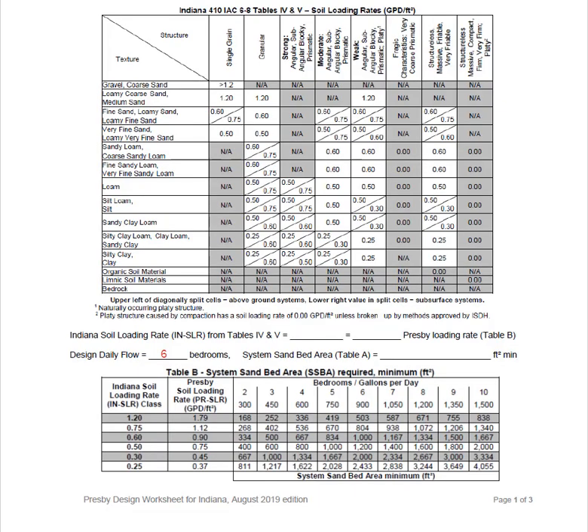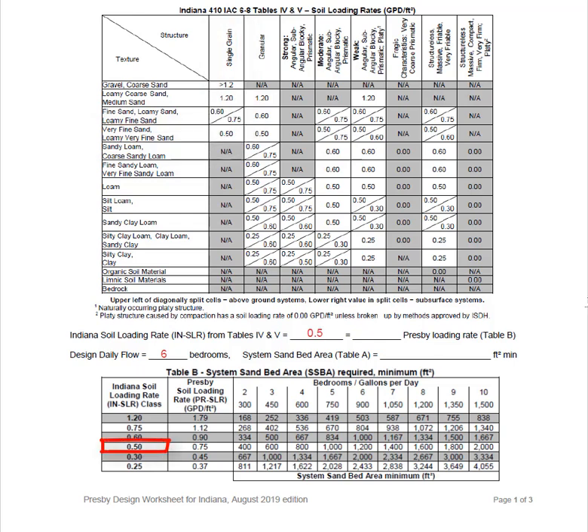In step number two, we're going to calculate the minimum system sand bed area. Let's find the row with very fine sand and then find where it intersects with the single grain column. This value is 0.5 gallons per day per square foot. Now let's find the corresponding Presby loading rate in table B. Once we find 0.5, we move directly to the right and find the Presby loading rate, which in this case is 0.75 gallons per day per square foot. We will start at the 0.75 loading rate and move to the right until we intersect the column for six bedrooms. In this case, we will need at least 1,200 square feet of system sand bed area.